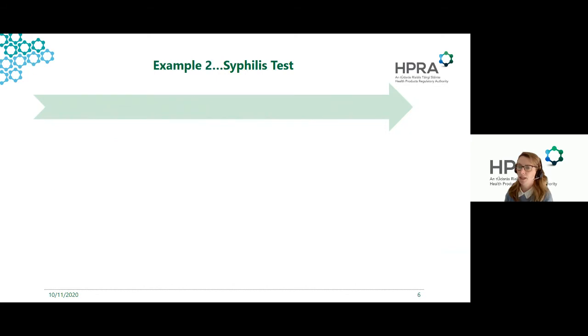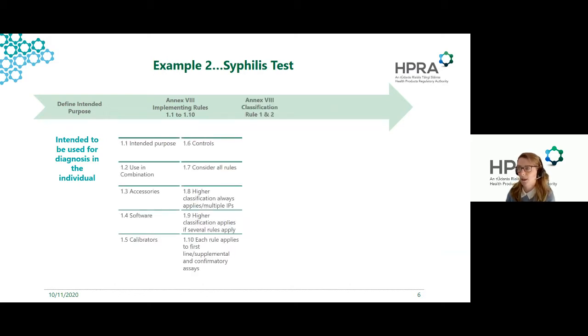However, with a different intended purpose, the intended purpose of diagnosis in the individual, again keeping in mind the implementing rules, you would start moving through your risk-based rules. At this time it wouldn't lie within rule 1, it wouldn't lie within rule 2. And when you come to rule 3, rule 3A would be applied. It's a sexually transmitted agent, and in this case it would be classified as class C. So this is a good example of the intended purpose and how it governs the eventual classification of the device.